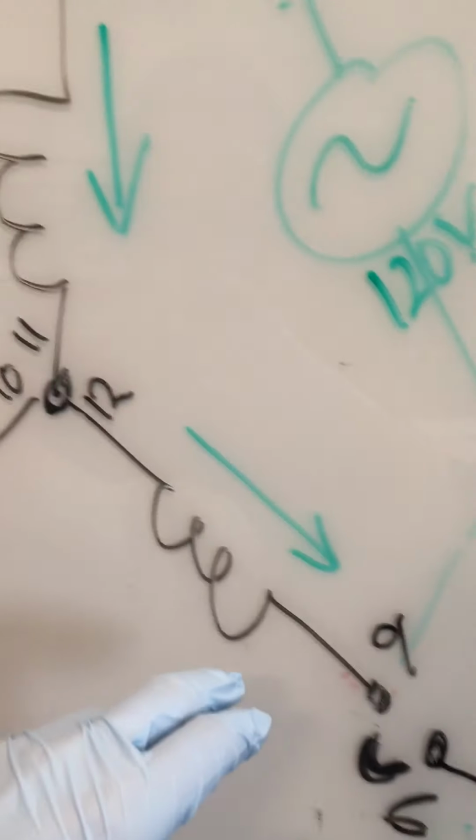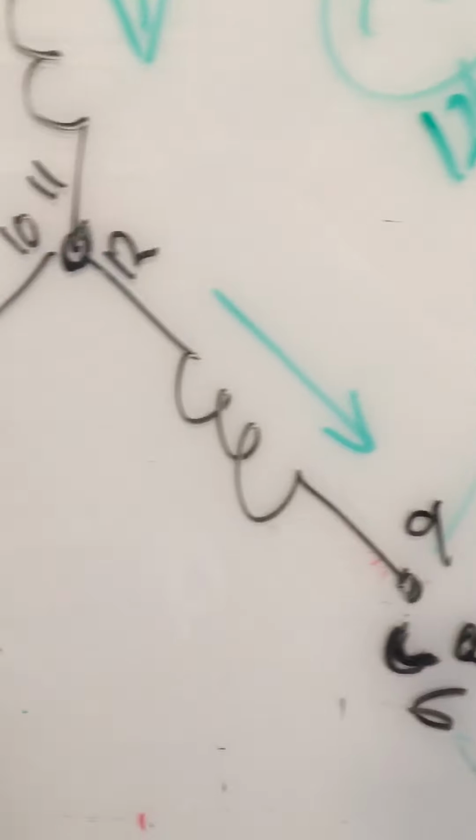Then we added in voltage from the system, and we would connect volts from 8 and 9, and then we'd go to the far side and measure. Whatever had the lowest voltage of the three smaller sets of two would be the farthest from the voltage we put in, so that means it would be the opposite. So for 8 and 9, it would be 1 and 4, and for 8 and 7, it would be 3 and 6, and so on.